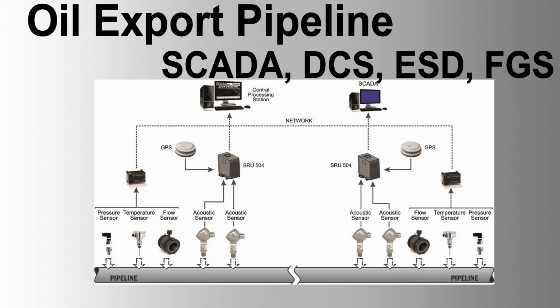Key control elements and their roles. 1. Safety Network. Function: handle ESD and FGS functionalities with dedicated SIL-certified safety network. Components: Safety Manager Stations, SMS, ESD PLCs, redundant Ethernet links. 2. Process Control Network, PCN, dedicated to process control monitoring and interfacing with other subsystems. Components: RTUs, PLCs, communication links, fiber optic or wireless. 3. Supervisory Control Network, SCN. Function: provide process control window to local station control systems, maintain data flow to master SCADA servers. Components: local SCADA servers, real-time process data flow, master SCADA servers.